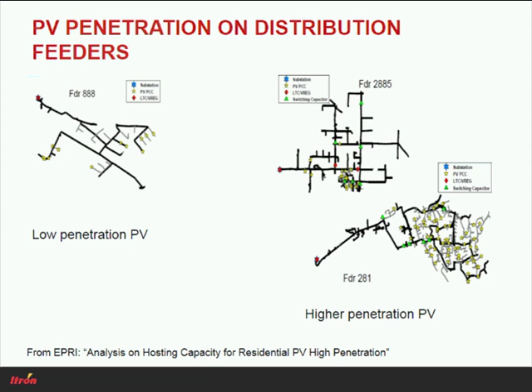We have to remember that photovoltaics has different characteristics. Again, it's intermittent. It depends on the sun. It depends on other factors. EPRI has done some work on looking at the effects of high penetration PV on distribution feeders. There are a number of factors that get affected in distribution feeders by high PV penetration. There can, again, be voltage imbalances. There can be overvoltage. High penetration PV can increase the number of faults that occur on a distribution feeder. You can get unintentional islanding, or sympathetic tripping that leads to unintentional islanding.